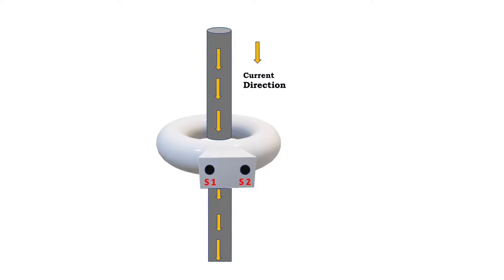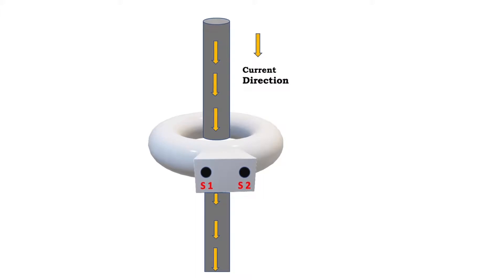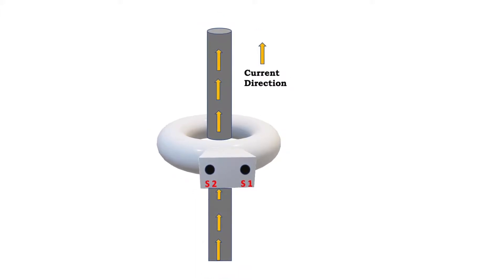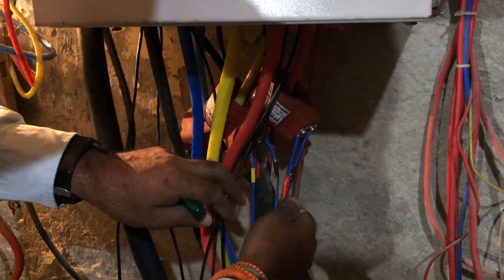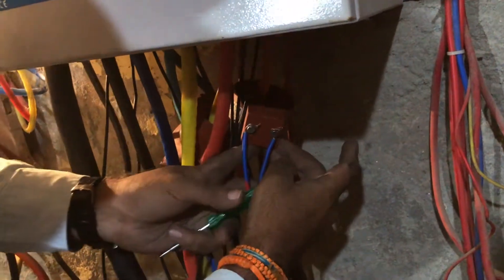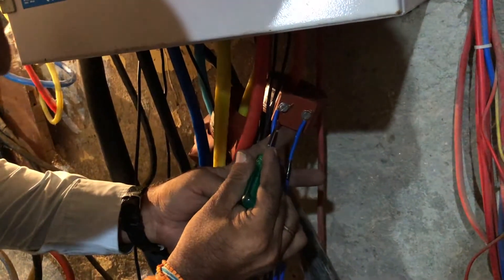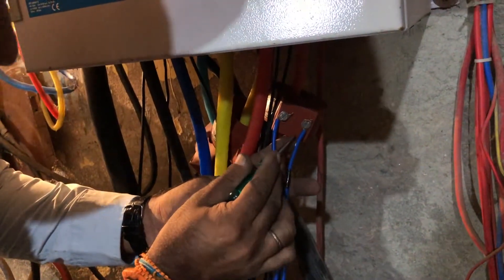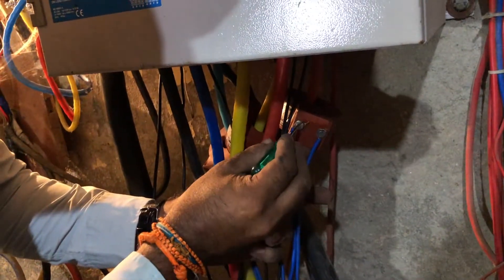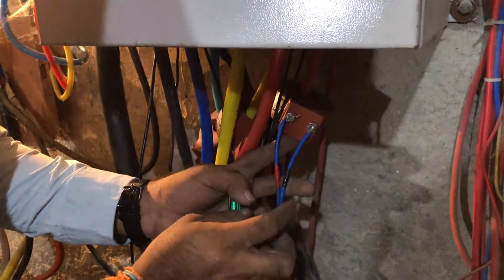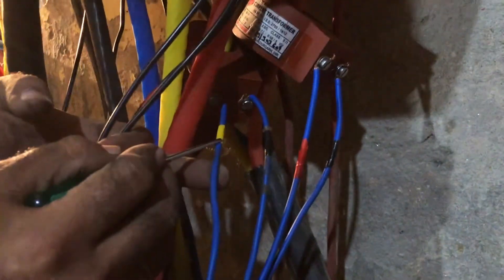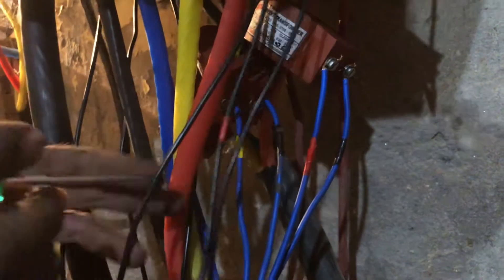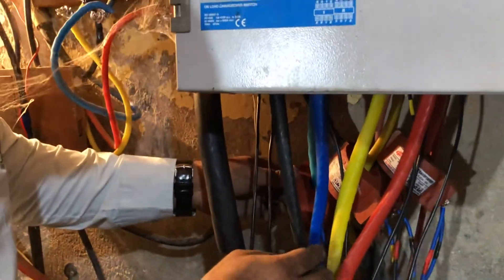We will do the CT connections accordingly. S1 comes to the left when the current direction is down, and when the current direction is up, S2 comes to the left. Now we'll make the connections onto the ACDB. For each RCT, S2 is connected to the neutral and S1 is connected to the line voltage. The CT direction can be determined by the right-hand thumb rule. We replicate this strategy for all other CTs: for Y phase, S1 to line and S2 to neutral; for B phase, S1 to line and S2 to neutral.